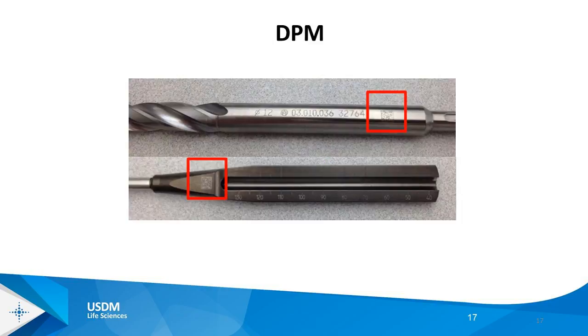We could go back to the notions of direct part marking. Obviously, this was the original envisioned approach for identifying implants. There are many implants that can be direct marked or direct part marked. In this case, laser etching, for example, of a data matrix on an implant or an instrument. However, there are many devices that are much too small, or their geometry is much too complex to allow for this. So there are some devices for which this might be a solution.